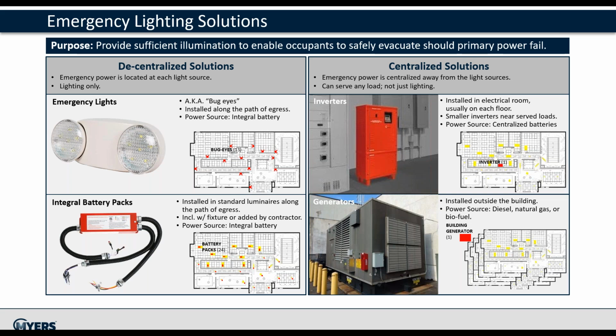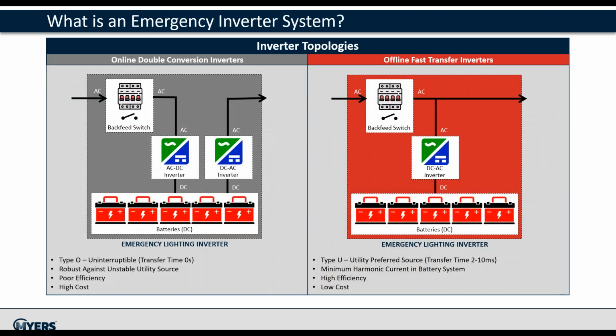Generators are located outside the building with power sources for emergency operation coming from diesel, gas, or biofuel. Within the inverter category, there are two topologies: online double conversion and offline fast transfer. Double conversion systems have two independent power sections, an AC to DC converter and a DC to AC inverter, as shown in the diagram.